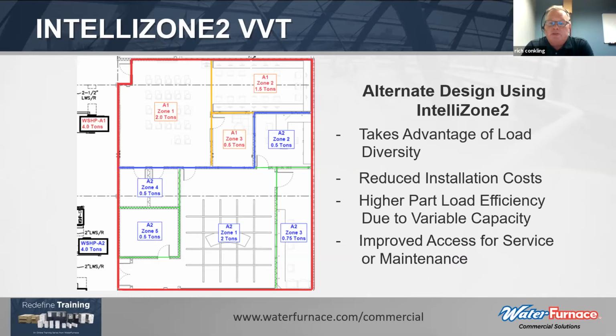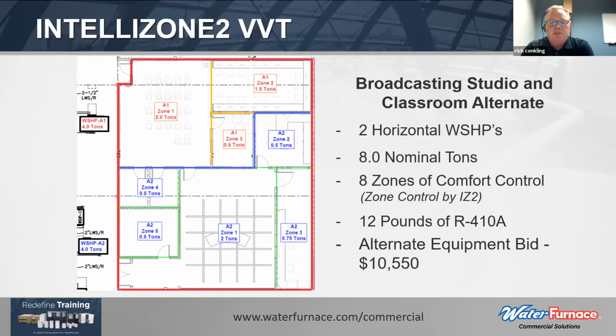We can take advantage of reduced installation costs. We can also take advantage of higher part load efficiencies due to the variable capacity of the compressor and the blower motors. And then again, because they're both located in the hallway, we improve access for service and maintenance and completely eliminate that small unit above the office. In that alternate design, we've got two units totaling 8 tons of nominal capacity. We go to 8 individual zones of comfort control in this, and we go from 14 to 12 pounds of refrigerant at an alternate bid cost of just over $10,000.